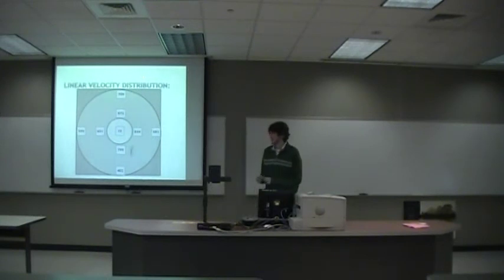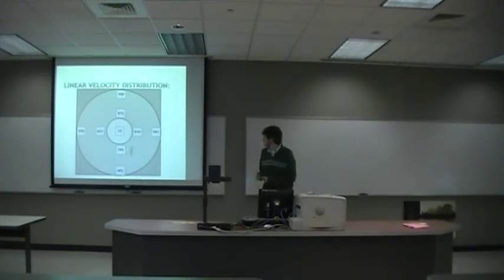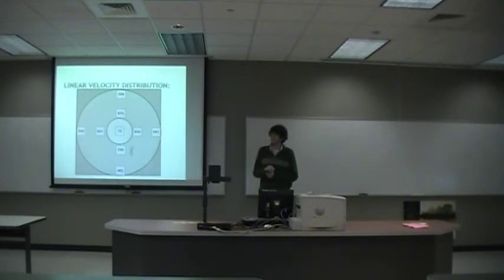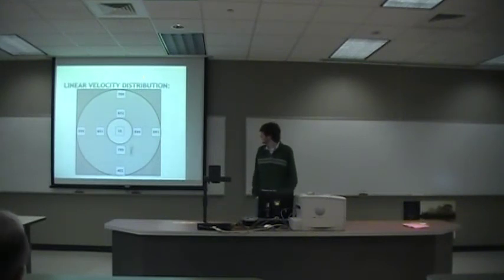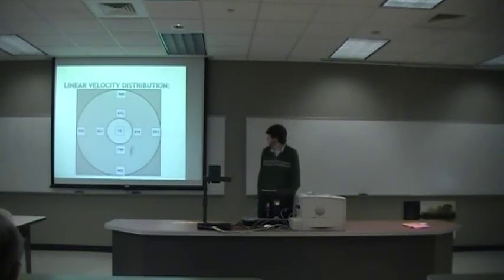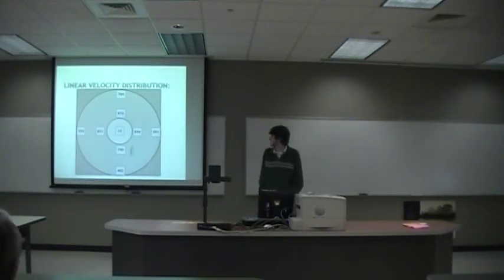Compiling all the data, this is basically what the box fan looks like with the velocities we got at each point. It's approximately 800 feet per minute on the inner radius, but the outer radius varied — the sides were around 600 feet per minute, with the bottom reading a lot lower than the top.